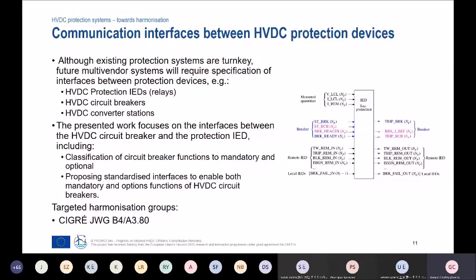Here we look at the interfaces required for basic operation, for example the trip signal between the protection IED and the circuit breaker, and also the circuit breaker functions which might be optional and not applicable to every protection system or every circuit breaker, for example current limiting on a circuit breaker, which might not be possible for every topology.